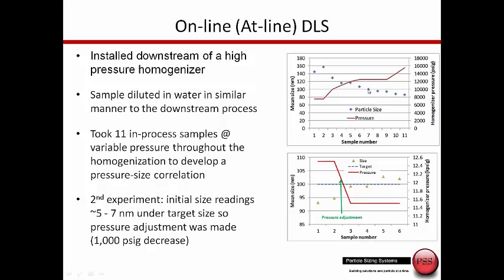Once the customer understands what is the optimum pressure, in this case the customer wanted to generate particles right at 100 nanometers, then as they start doing batches, you see at the beginning the particles are actually undersized. So they reduced the pressure and then started generating the particles exactly in the size range desired. This is a unique capability of being able to take the NICOMP optics and algorithm and apply it to online measurements.